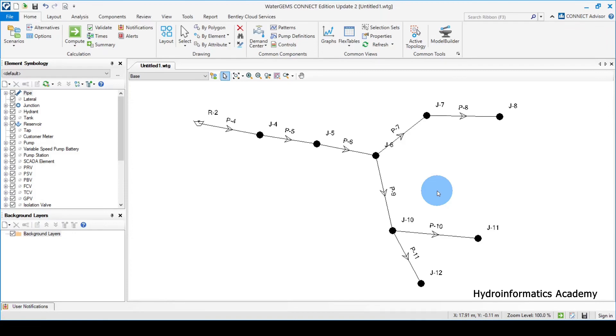The next important thing is to optimize our model using the following parameters. The first one is velocity — we need to make sure that our velocity ranges from 0.4 meters per second all the way to at least 1.5. This varies from country to country. The second parameter is unit head loss — we need to maintain unit head loss at around 5 meters per kilometer all the way to 10 meters per kilometer.